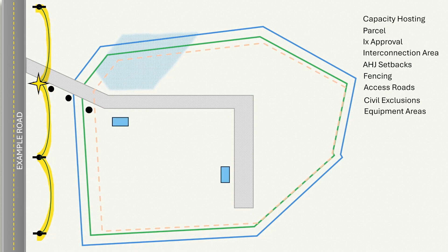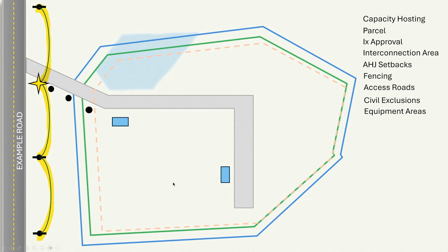Next up is equipment areas — making sure that we leave space for major electrical equipment. This could be as large as a substation or smaller pads. We want to locate them in strategic locations that are near the access road and not too far in a corner where they're hard to reach. We also want to space them relatively evenly throughout the site so that we're making long runs in medium voltage cable, not DC string wire, combiner box output wire, or low voltage AC conductors.